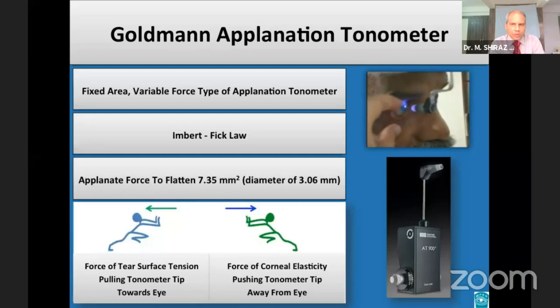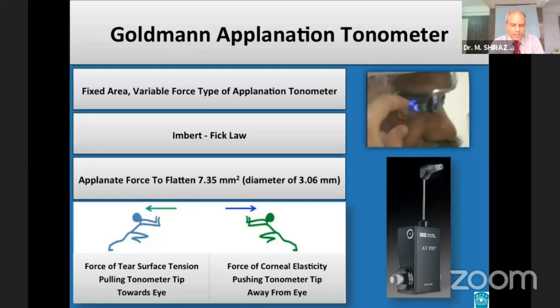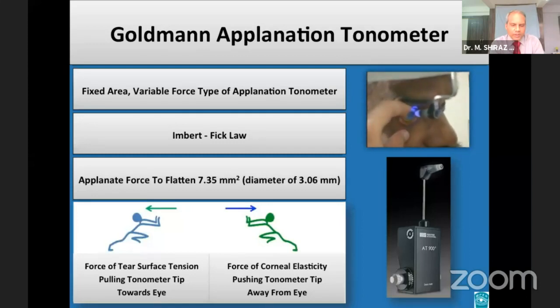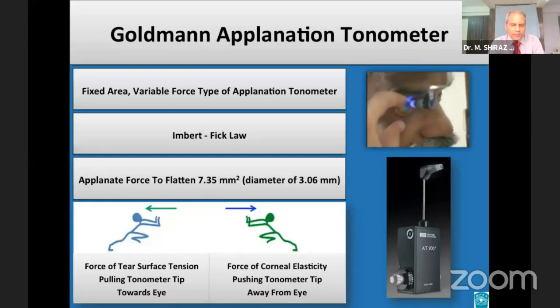The Goldman applanation tonometer is based on the Imbert-Fick law. GAT uses an applanating force to flatten a constant area of 7.35 mm squared. At this selected area, the forces of tear surface tension pulling the tonometer tip towards the eye and the corneal elasticity pushing the tip away are almost equal and opposite.